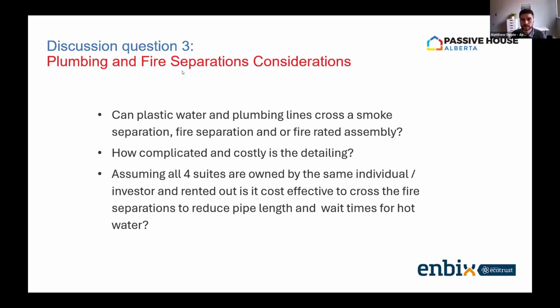I'd agree with everyone who's spoken in terms of plumbing not being an issue moving between suites. I do think that if we've got a central ERV, that's where we can run into challenges with fire and smoke dampers. There's a change in the 2015 building code edition that requires smoke dampers wherever you have a rated wall in a residential building crossing suites, as well as fire dampers. The fire damper is pretty simple, but a smoke damper costs about 10 times as much, so that can be a challenge. I know Rod mentioned keeping duct sizes small enough to avoid needing fire smoke dampers, but that solution depends on your authority having jurisdiction.